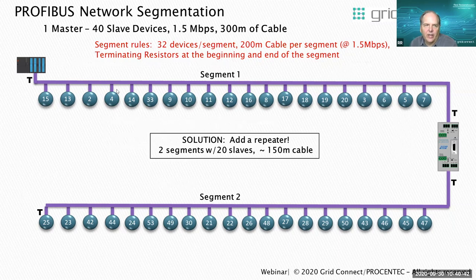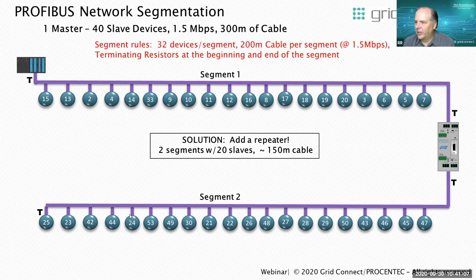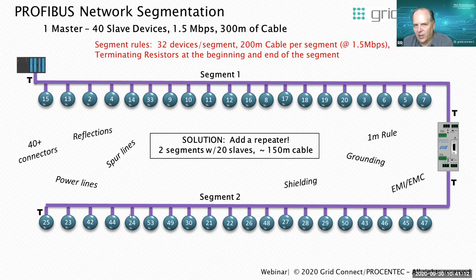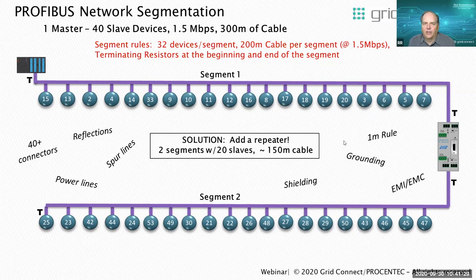We've added a repeater — now we have two segments, each with 20 slave devices and about 150 meters of cable. In fact, this is how PROFIBUS network design has been done for years; I've seen plenty of networks laid out this way that work well for a long time. However, stuff does begin to go wrong. Outside influences include power lines, grounding and shielding problems, EMI/EMC interference, not understanding all the PROFIBUS rules like one-meter rules, and reflections from interference. We also have 40-plus connections that were hand-wired, possibly without proper stripping tools, so wire nicks over time turn into wire breaks or near wire breaks causing intermittent communications.